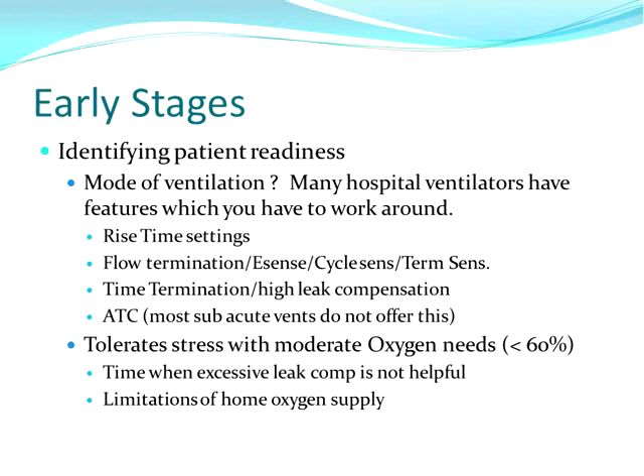For example, on the Puritan Bennett 840 ventilator, it's a percentage. In the Draeger ventilators, it's actual time. On most of our home care and subacute ventilators, rise time is in some sort of profile, although some ventilators may have more option settings for rise time. So the key is really understanding how rise time works on your critical care ventilator and then making an even transition to the ventilator that you're using in subacute. That's why it's really important, critical care therapists, that you work together with the home care therapist. The ventilator that may be coming in for the transition may not be something that you're completely familiar with, so you may want to take a look at that.